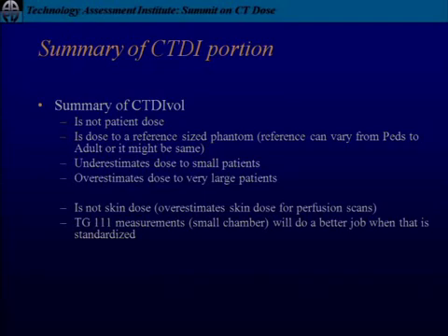Okay, and one other, so we've talked about this before too, is that some scanners, at the end of it, you'll get this little dose report. You've seen that? And sometimes in our scanners, they report the average effective mAs for the whole scan. Okay? Other scanners don't. So it's a little stickier. What she's talking about is a little more painful, but the information is there. It's just painful to extract.